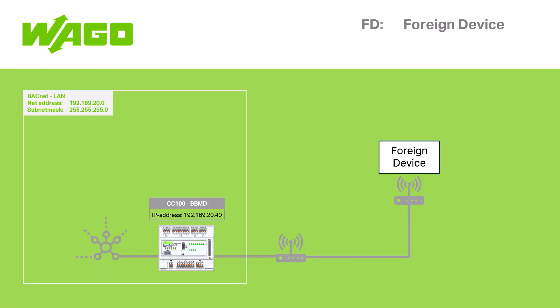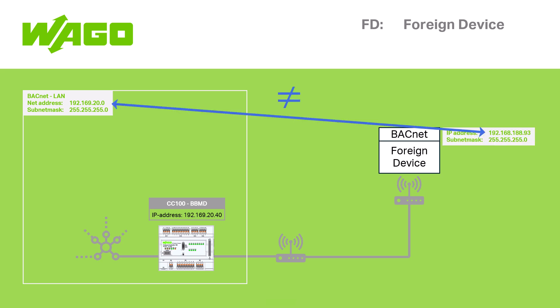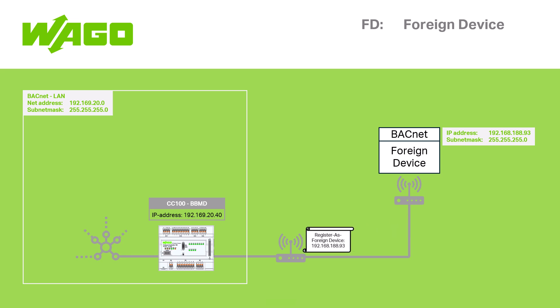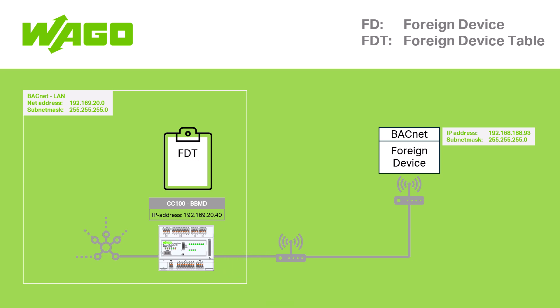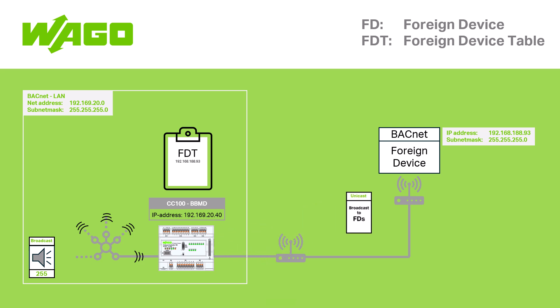A foreign device is a BACnet device with an IP address that is different from the BACnet IP network. In order for the BACnet device to join the network, the foreign device can send a register as foreign device message to the BBMD of the remote BACnet IP network to be registered in the BBMD's foreign device table. Once registered, the BBMD will create a forwarded message when it receives a local broadcast and send it to any foreign device currently registered in its FDT.